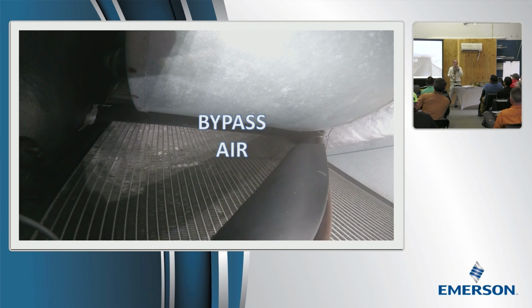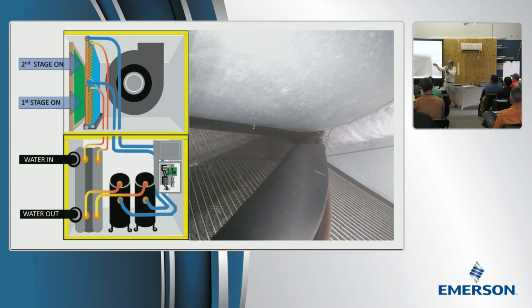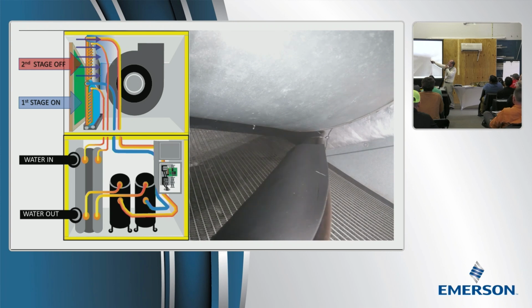And the guys thought that it was throwing water off the coil, which is often a thing that you look for. So we put a GoPro camera in there, and we recorded it, and we saw the fog. And what it's doing is, the water source unit is a two-stage coil, but when it's a stacked coil, it's not an interlace coil. So when the second stage goes off, the air comes in raw. And the raw air hits the cold cabinet and just makes a mess.